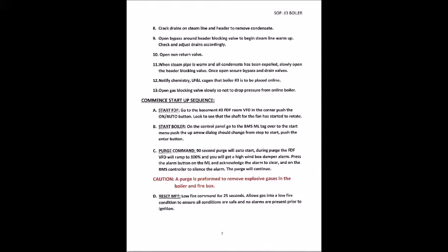Step 12. Notify chemistry, LP&L Cogen that boiler number 3 is to be placed online. Commence startup sequence. A. Start forced draft fan. Go to the basement number 3 FDF room, forced draft variable drive in the corner. Push the on auto button. Look to see that the shaft for the fan has started to rotate.